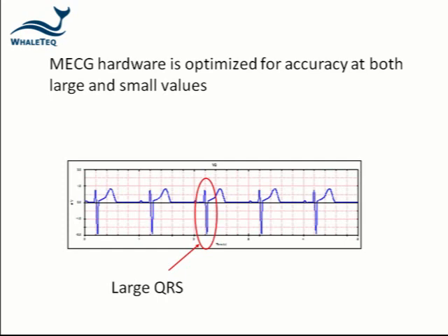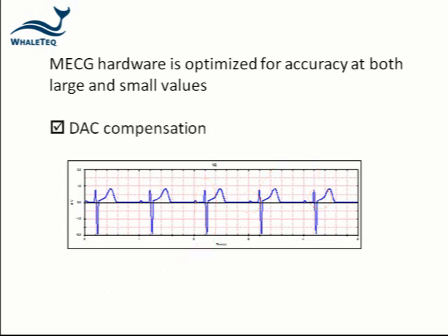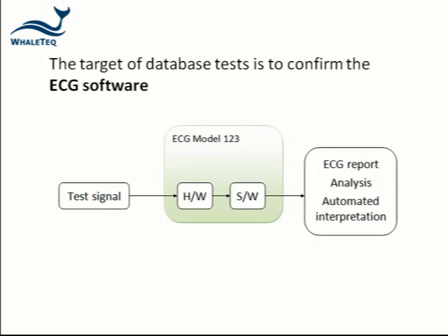The MECG hardware has been optimised to provide high accuracy for both large and small values. This is necessary as some waveforms have a large peak amplitude but contain important low-level values such as voltages in the ST segment. DAC compensation and a digital reverse Wilson terminal for V1 to V6 have been used to achieve this goal. Generally, the target of a database test is to confirm the accuracy of analysis in the ECG software.